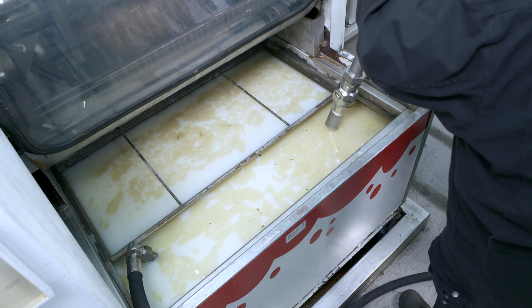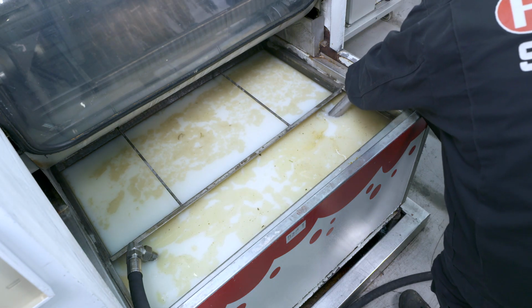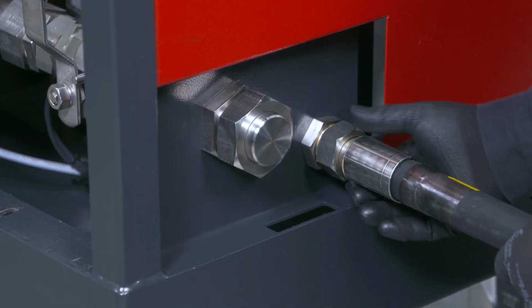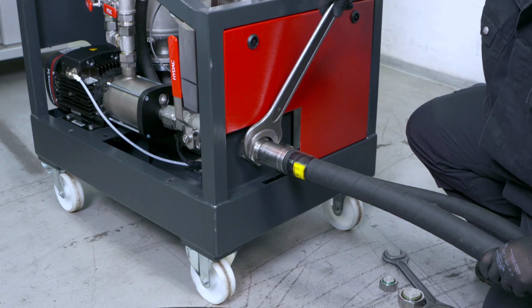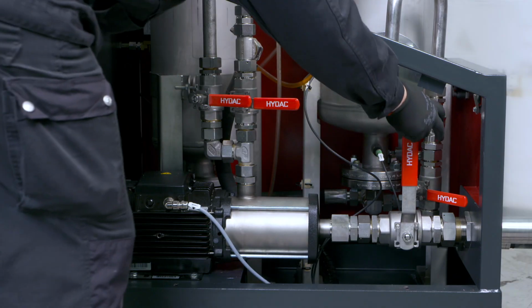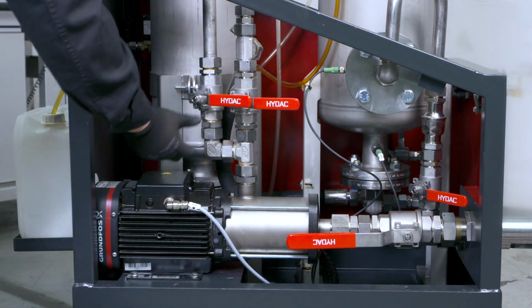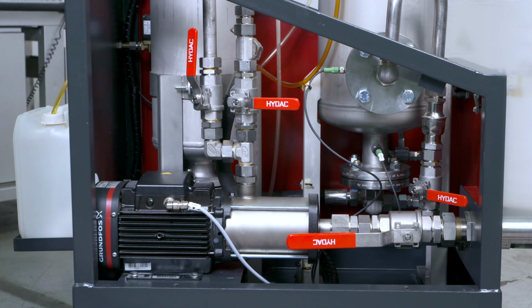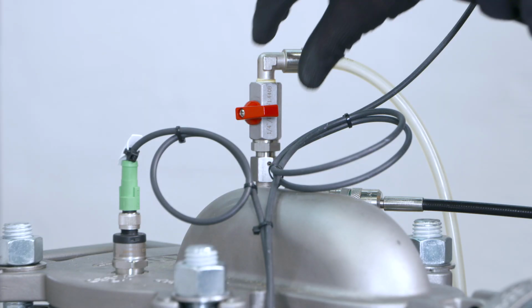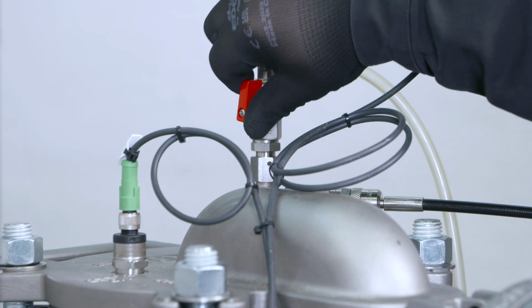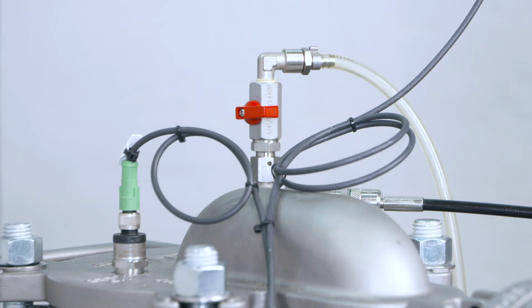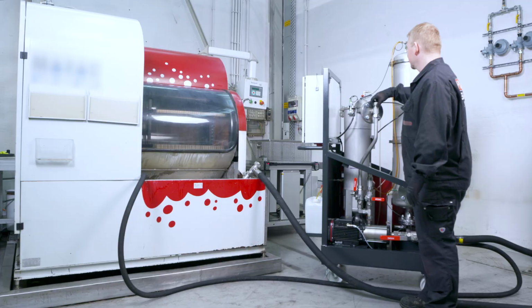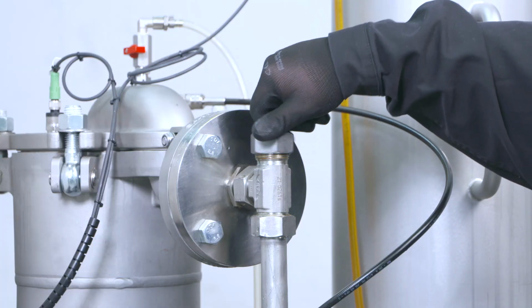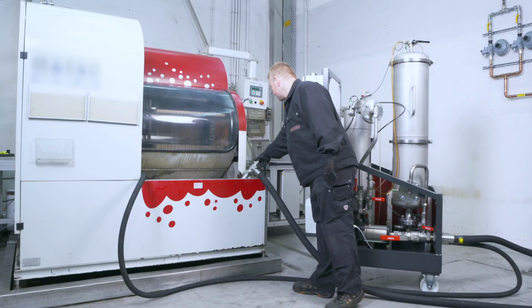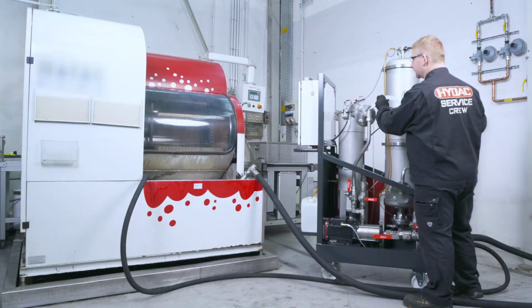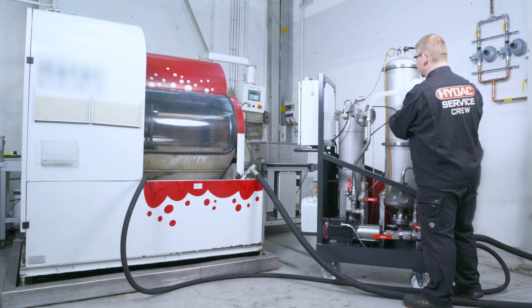Commissioning. After hanging the hoses into the tank, the suction and pressure connection is fitted to the OLSW with hoses. Then 2 valves are opened: the valve on the suction side of the cleaning device and the valve to the wombat. The venting valve on the wombat filter is opened briefly in order to ensure that the pressure is released from the system. Both T-pieces must be opened in order to pre-fill the suction pipe and allow the air to escape. Water should always be added to the higher side until the other end of the hose is completely full.